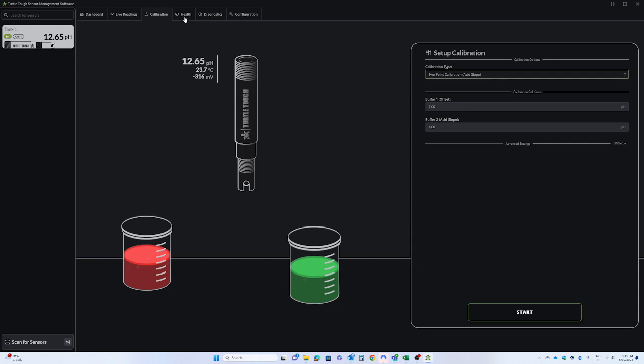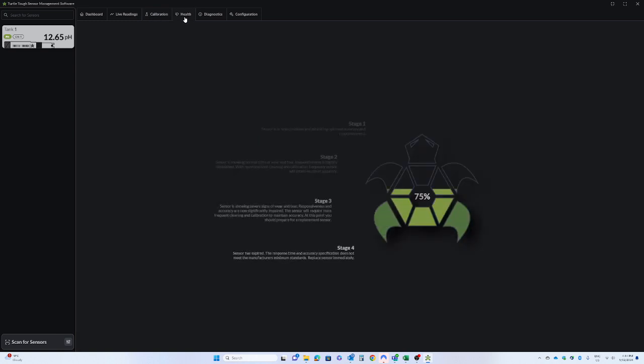Moving along to our next tab, we have the Health tab, and this is an automatic diagnostic feature that takes a lot of the hard work out of interpreting what all the various values mean that are coming off the sensor. There are 4 stages to a sensor's health. Stage 1 essentially shows us a sensor that's in excellent condition, exhibiting its optimum response and accuracy. And from there, the probe decreases in 25% intervals until we reach stage 4. And that's basically a sensor that's expired and needs to be replaced.